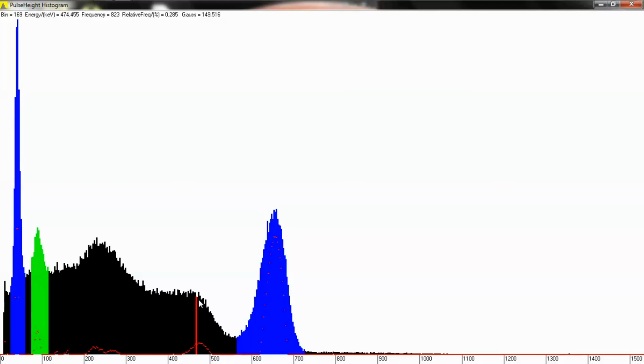It's kind of the opposite. It's photons that have reflected off of the crystal at an angle, but they're not really reflecting backwards. They're just at a slight angle. And then you have this whole entire continuum, this Compton continuum here. This is called the Compton plateau, of various scattered photons ranging in their angle of scatter because they get bounced off of the crystal. They don't all perfectly get absorbed. And then you have the Compton Peak, you have the Compton Plateau, you have the backscatter peak, the X-ray fluorescence.